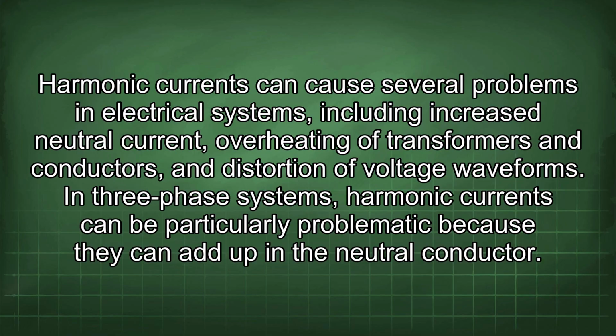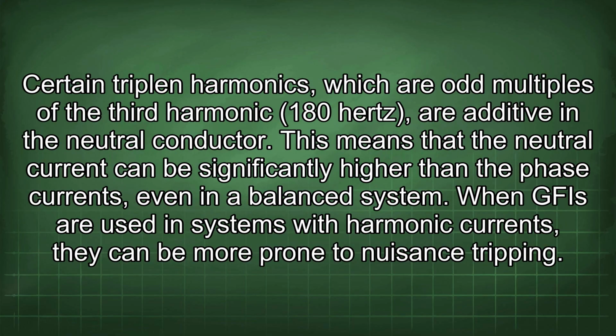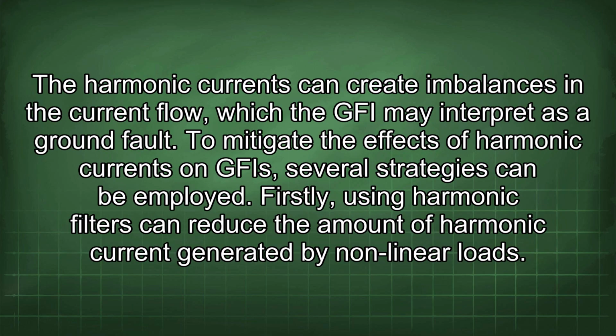of voltage waveforms. In three-phase systems, harmonic currents can be particularly problematic because they can add up in the neutral conductor. Certain triplen harmonics, which are odd multiples of the third harmonic, 180 Hz, are additive in the neutral conductor. This means that the neutral current can be significantly higher than the phase currents, even in a balanced system. When GFI are used in systems with harmonic currents, they can be more prone to nuisance tripping. The harmonic currents can create imbalances in the current flow, which the GFI may interpret as a ground fault.